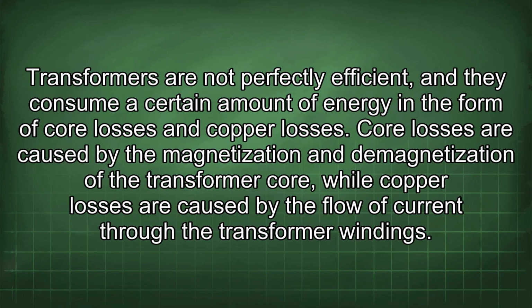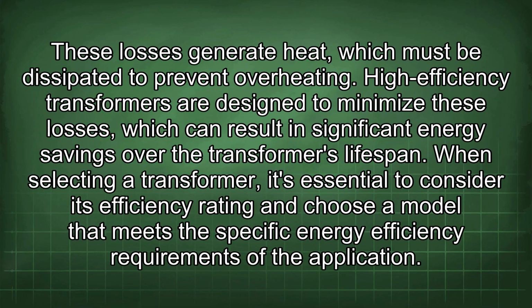Transformers are not perfectly efficient, and they consume a certain amount of energy in the form of core losses and copper losses. Core losses are caused by the magnetization and demagnetization of the transformer core, while copper losses are caused by the flow of current through the transformer windings. These losses generate heat, which must be dissipated to prevent overheating. High-efficiency transformers are designed to minimize these losses, which can result in significant energy savings over the transformer's lifespan.